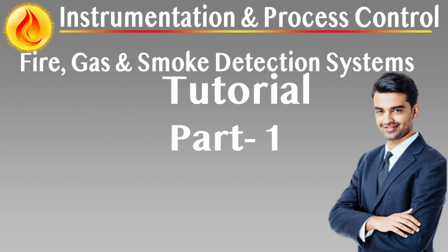Avoid direct exposure to washdowns, wind gusts, and particulate fouling. Calibration gas concentrations must remain below 60% LFL. Detector integration requirements. Each point detector must integrate into the IPS using either analog 0-20 mA signal or potential free contact outputs as specified by the control system design.